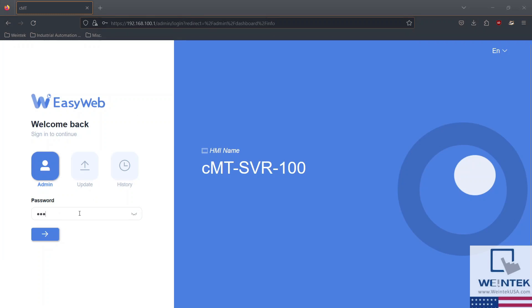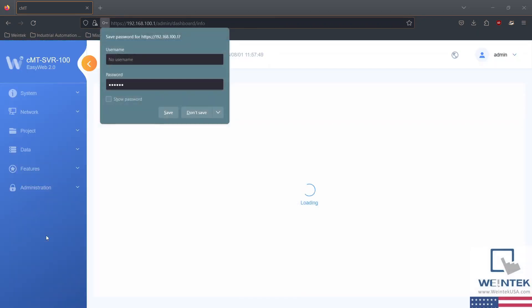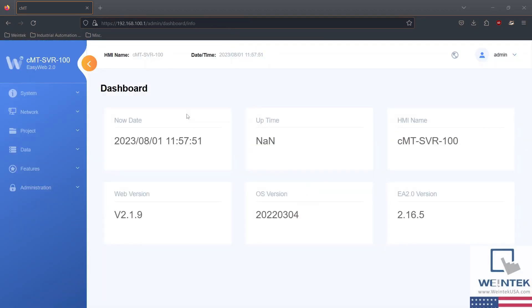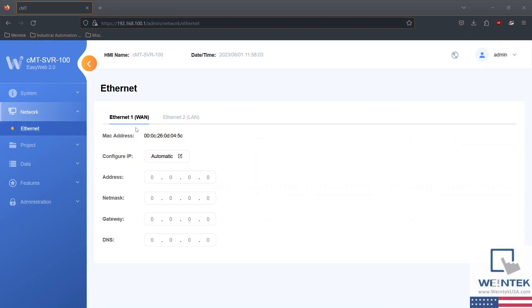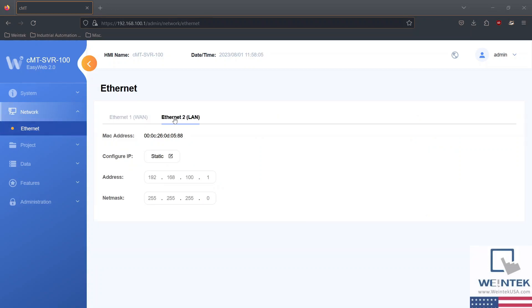Next, you'll be prompted to enter your device's password. 111111 is the default password for all Weintek HMIs. Within our EasyWeb 2.0 dashboard, head on over to the network tab and select Ethernet. Next, select the Ethernet port in which you would like to configure network settings. You have the option to statically assign an IP address and subnet mask, or you can automagically receive network configuration via DHCP server.